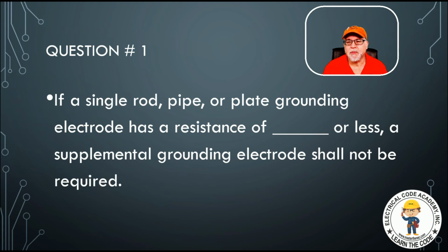So I think most of us, if you're going to put a rod in anyway, probably put in two rods. Keep them 6 feet apart at minimum, and they're 8 feet long, and you drive them into the earth. If you hit rock at a 45, then you're able to lay them horizontally in the ground. Now, supplementing the ground rods or pipes or plates is a supplemental requirement that only applies to rods, pipes, and plates.